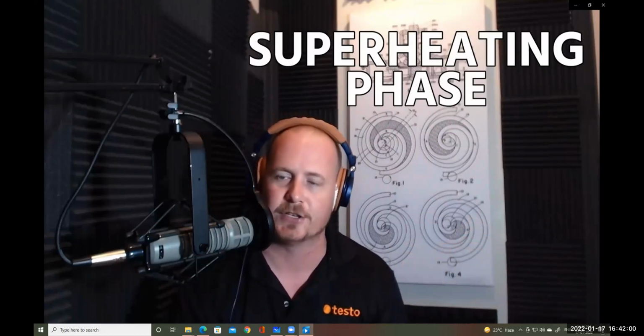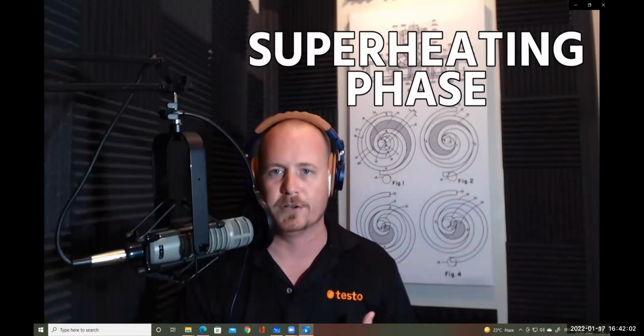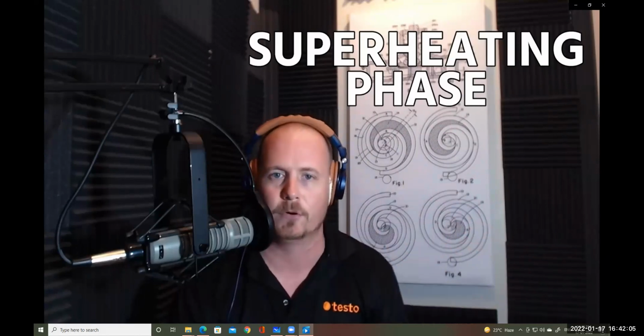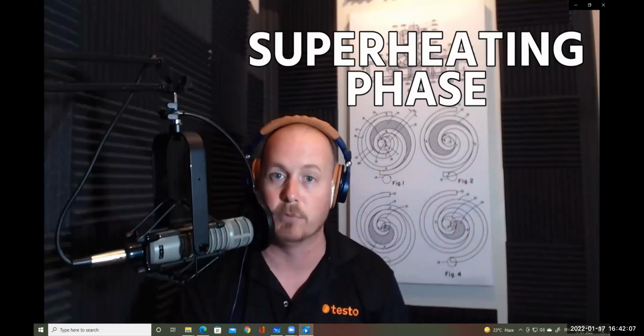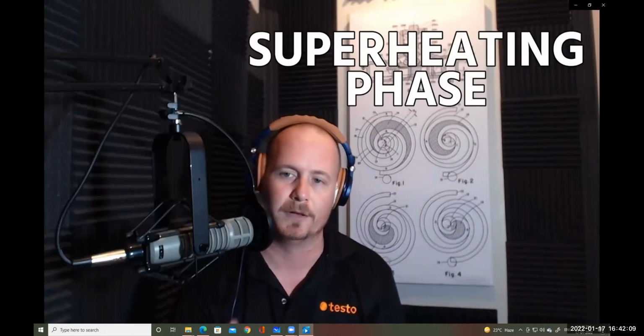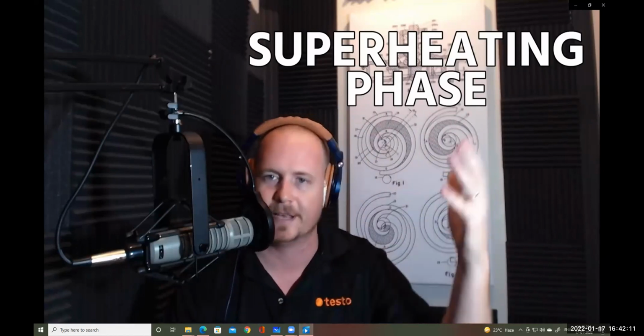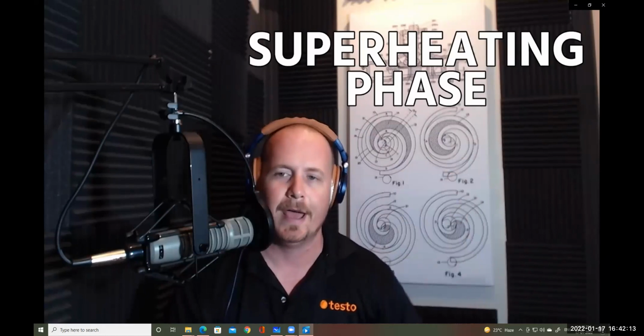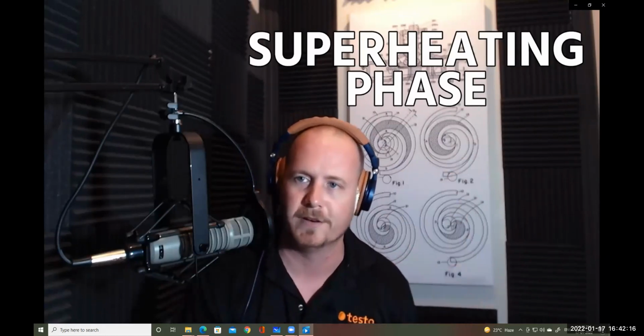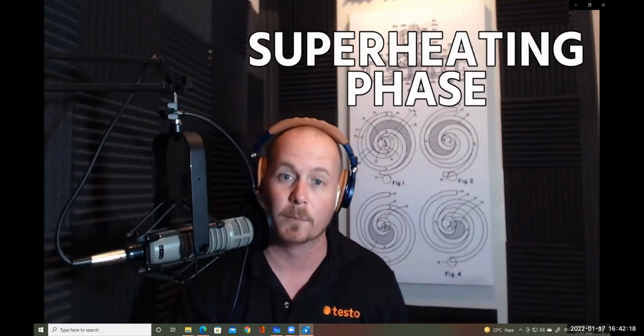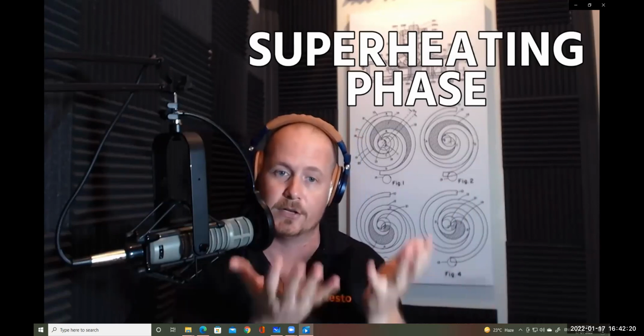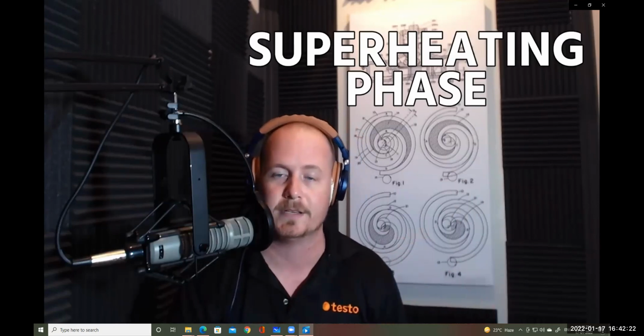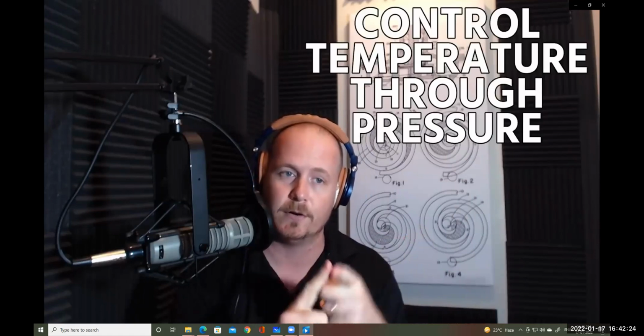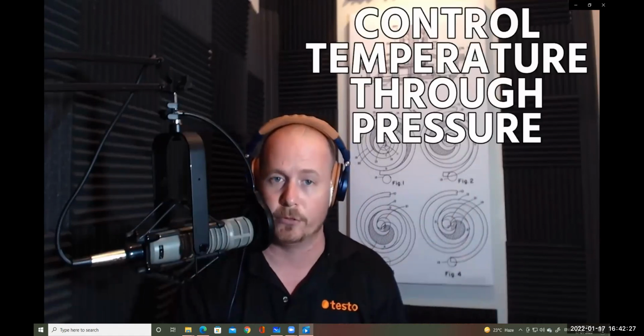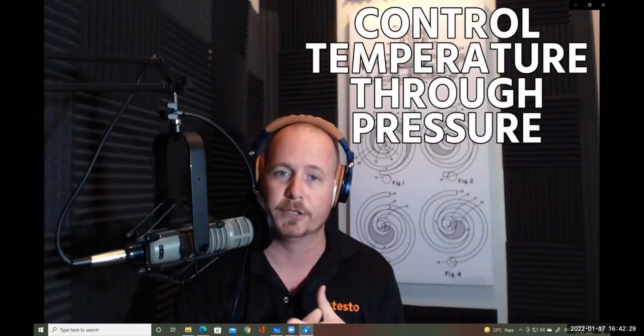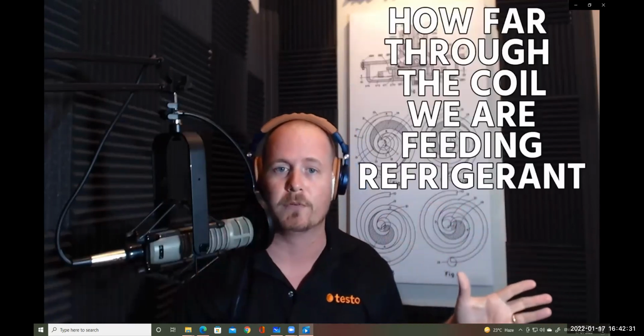That's all superheat is. It's just using temperature and pressure in order to tell us how far through that evaporator coil that liquid refrigerant is boiling. So how long through that evaporator coil is there still some liquid? It's going to start off at, say, 70% liquid refrigerant, and then it's going to go to 60, 50, 40, 30, 10, and then finally it will go to 0% liquid refrigerant, and that's when we can start to superheat. That's when that temperature can start to rise. So we're going to control the temperature of that boiling through that evaporator coil through pressure. And then we're also going to control how far through the coil we're feeding the refrigerant.